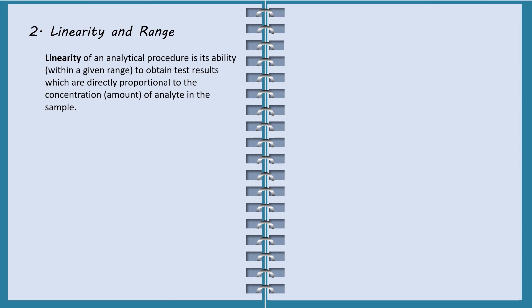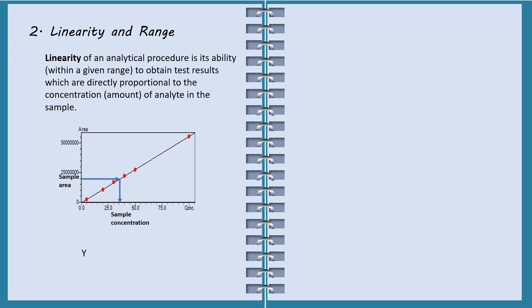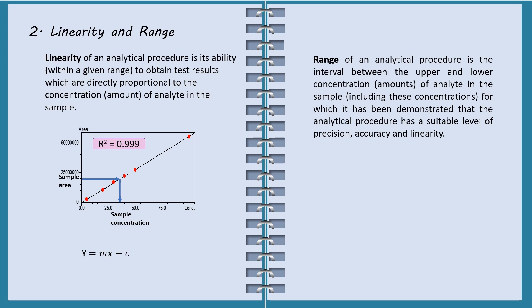Linearity of an analytical procedure is its ability to obtain test results which are directly proportional to the concentration of analyte in the sample. Within a given range, concentration of an unknown sample can be obtained via the calibration curve. Linearity of a calibration curve is often determined by R square value. According to the calibration curve displayed here, the range of this analytical method is between 5 to 100 ppm.